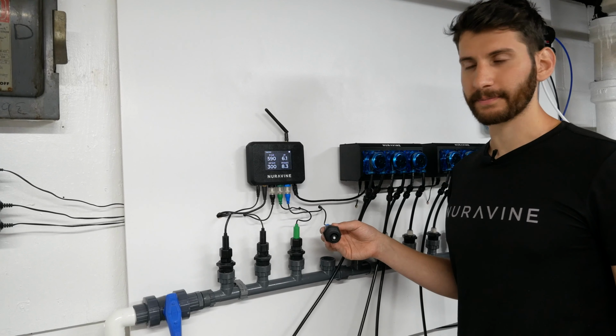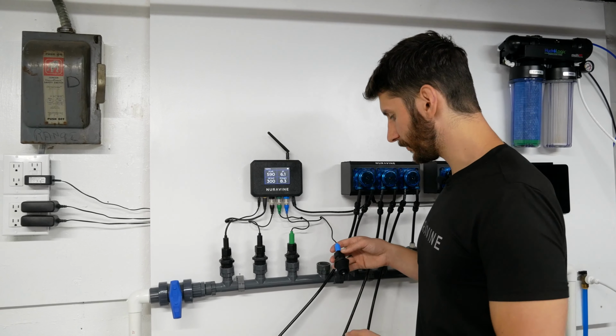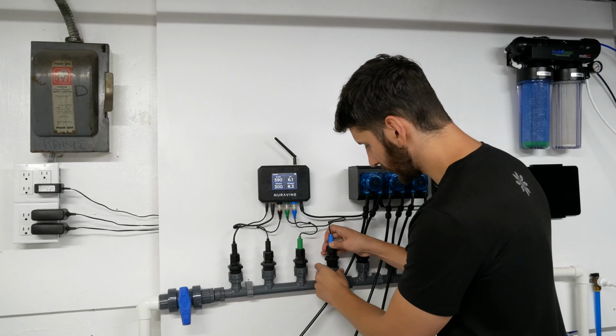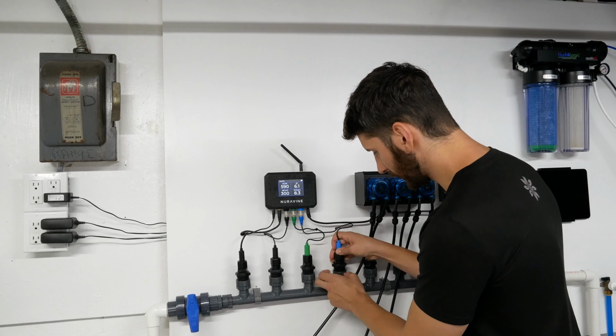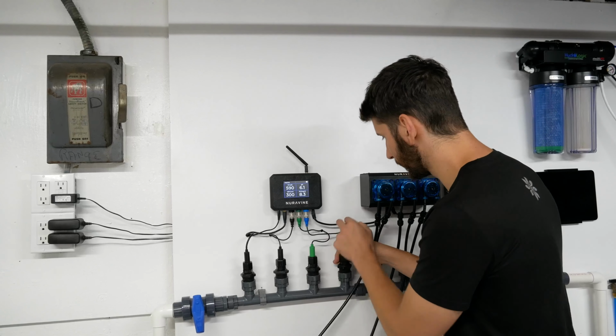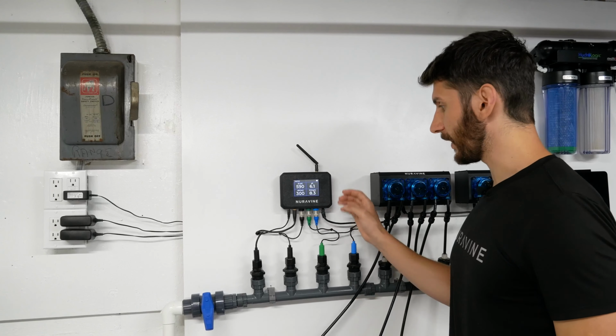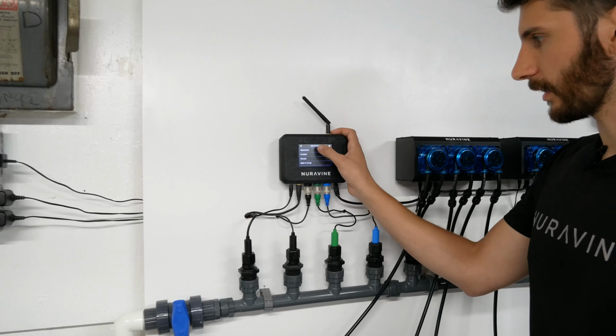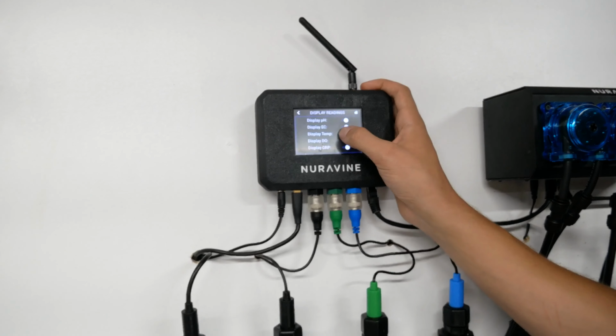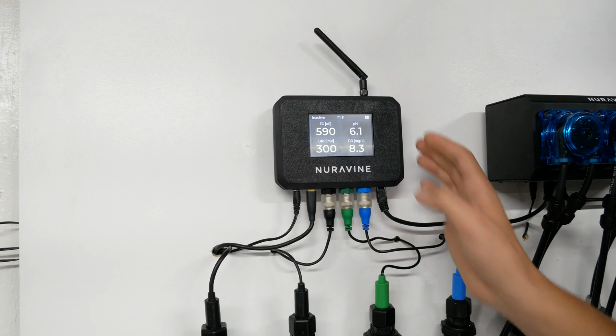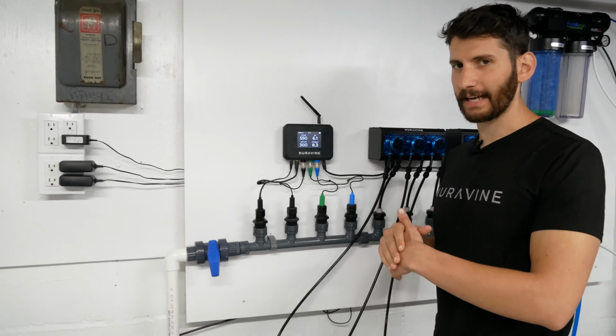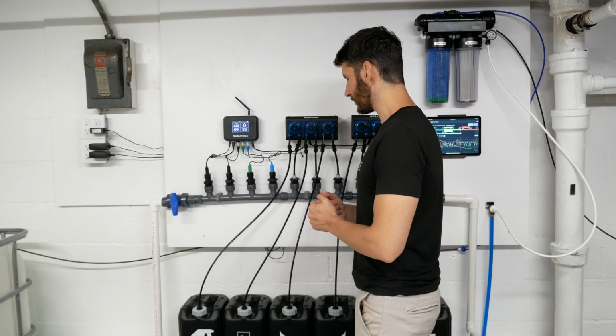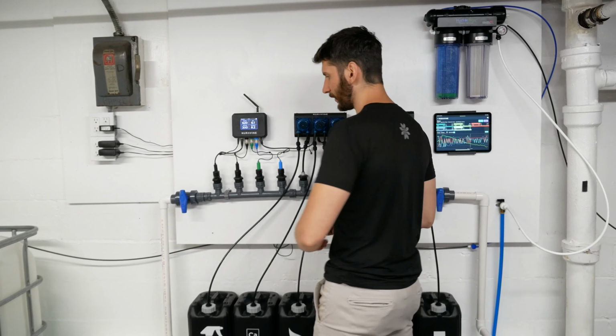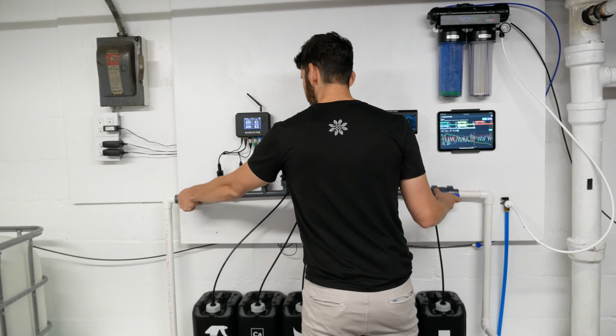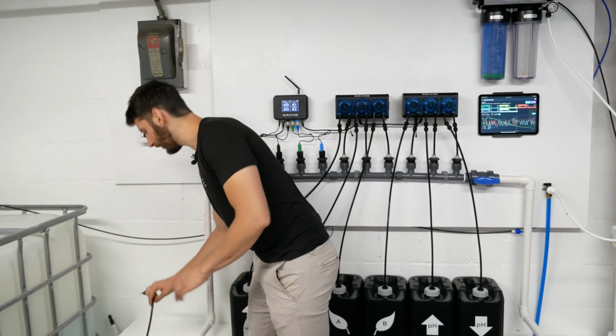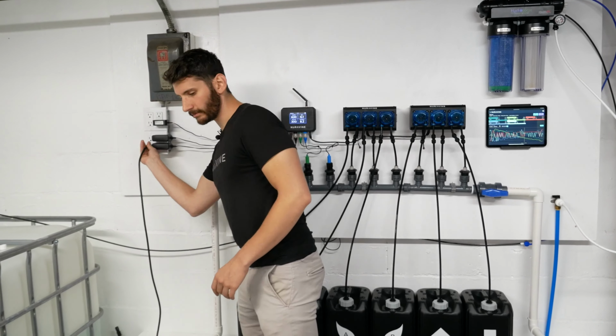so that means our calibration was good and we're done with the dissolved oxygen calibration. So now I'm going to take this probe and put it back into the manifold, like so. Make sure it's got a nice tight seal. And then finally we have to make sure we put our temperature back. So I'm going to go back into the menu, click on Sensors, do Display Readings, and turn back on the temperature. And we are done with our calibration of the dissolved oxygen, and now all the sensors are calibrated. Now that we've got all our sensors back in, we're ready to start using our system. So I'm going to now open up these ball valves, and we're going to plug back in our circulation pump, and we're ready to go.